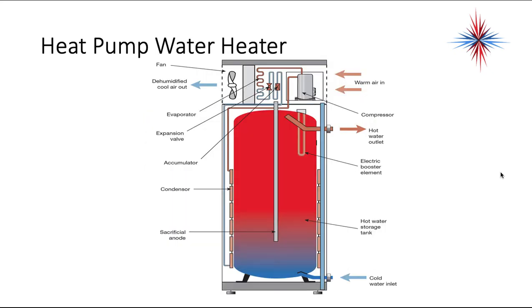I mentioned air to water heat pumps being domestic water heaters. If you're in an area of the country that has warmer temperatures, you might see these in someone's garage, or even sometimes outside, even though it's not recommended. What it's actually doing is circulating water. It's heating the water by de-superheating and condensing the refrigerant of a small refrigeration system.